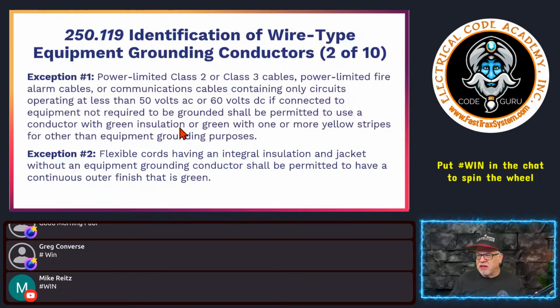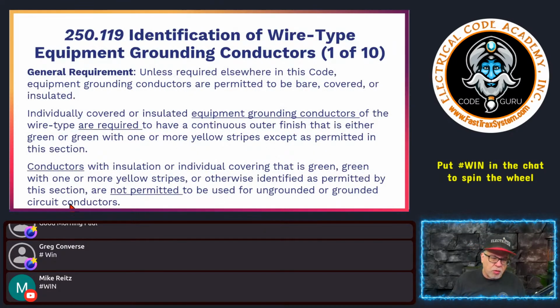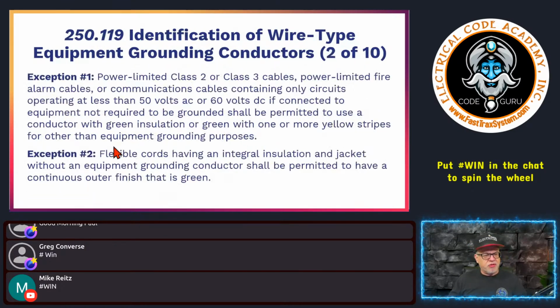So what are the exceptions to this? Identification, again, this is the requirement to be green. There are some exceptions to that rule. Exception 1 says power limited Class 2 or Class 3 cables, power limited fire alarm cables, and communication cables containing only circuits rated at less than 50 volts AC or 60 volts DC, if connected to equipment not required to be grounded, then it shall be permitted to use a conductor with green insulation or green with one or more yellow stripes for other than equipment grounding purposes. But you've got to meet these caveats, okay?